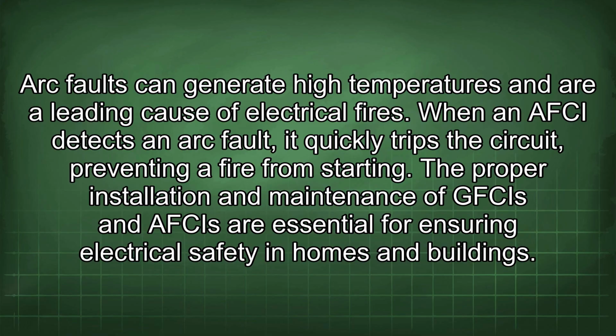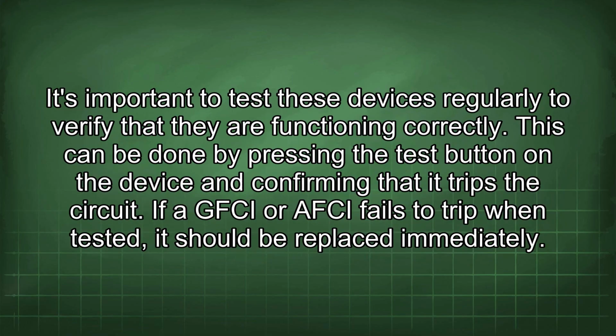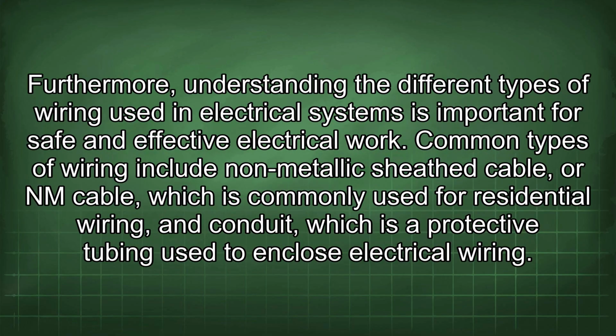The proper installation and maintenance of GFCIs and AFCIs are essential for ensuring electrical safety in homes and buildings. It's important to test these devices regularly to verify that they are functioning correctly. This can be done by pressing the test button on the device and confirming that it trips the circuit. If a GFCI or AFCI fails to trip when tested, it should be replaced immediately. Furthermore, understanding the different types of wiring used in electrical systems is important for safe and effective electrical work.